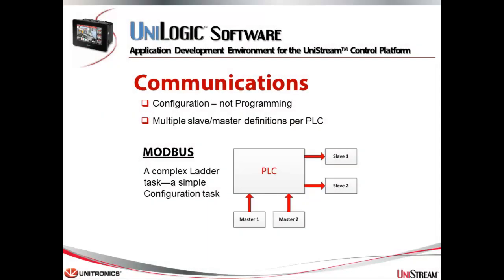Communications in UniLogic are completely independent of ladder. You carry them out by configuration rather than programming. This diagram shows a Modbus configuration. You can configure a single PLC to be master, to be slave, and to also be multiple master and multiple slave. This would be a very complex ladder task, but it is a simple configuration task.